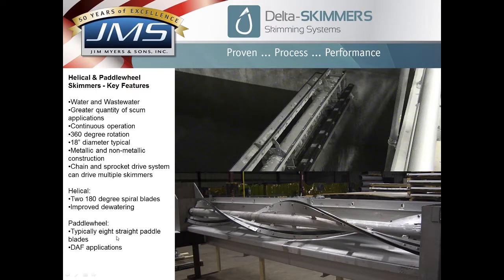We do that often. For the helical and paddle wheel skimmers, usually the change in elevation in water is about 2 inches or less. We can use larger diameter systems for basins that have a change in water up to about 4 inches or so, but after it gets that much change in water elevation, it gets too big, it gets impractical. Envision this paddle, look at the top one, if you have too much of a change in water elevation, you're not going to grab anything at the low end, and at the top you're going to be grabbing a bunch of water and discharging water into the trough, which is not what you want to do. So that's one of the limitations of these, the change in elevation in the basin.